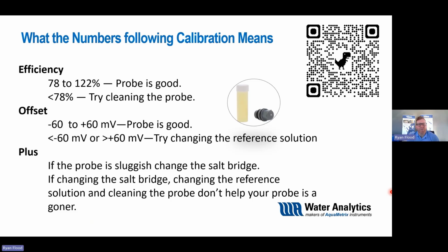So what do the numbers mean for calibration? So as we mentioned before, the efficiency, about 78 to 122, because you can be on either side of that spectrum from the efficiency standpoint. That's when you want to start saying it's time to maybe clean the probe. If you have an offset that's a little bit too far, maybe it's time to replace the reference solution. Again, that could be contaminated, or the salt bridge, its junction, could also be clogged. And again, you just need to clean it.